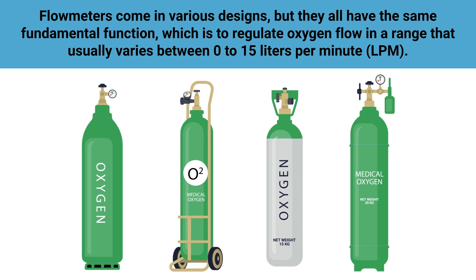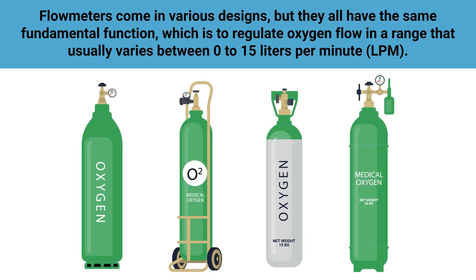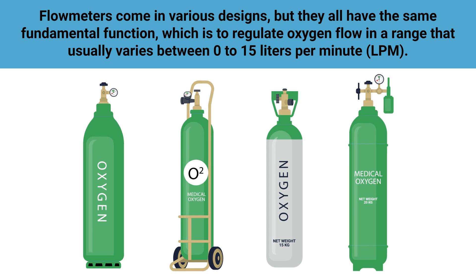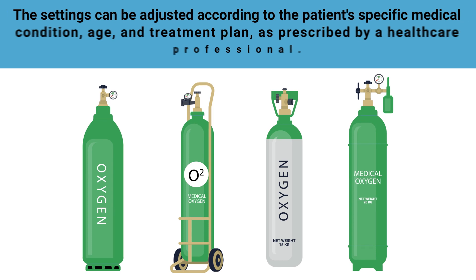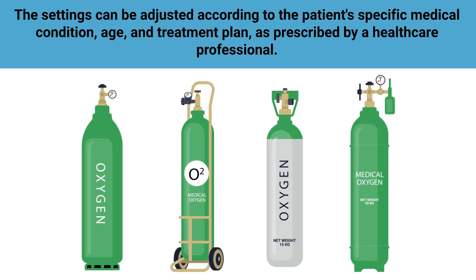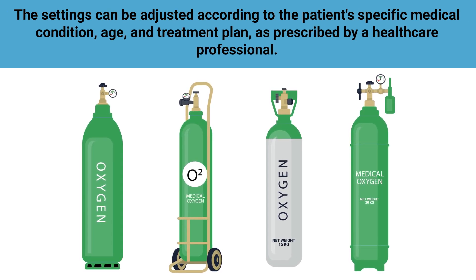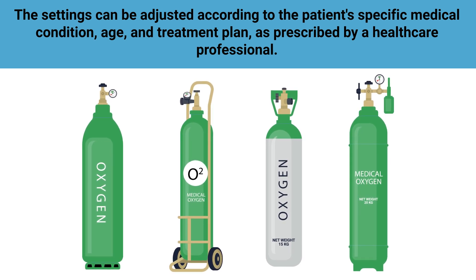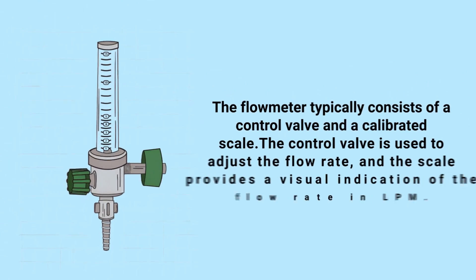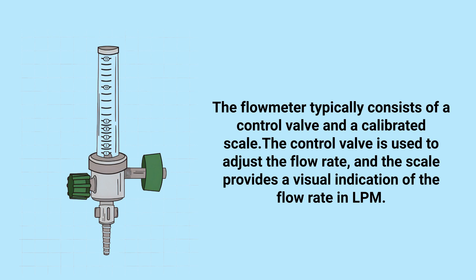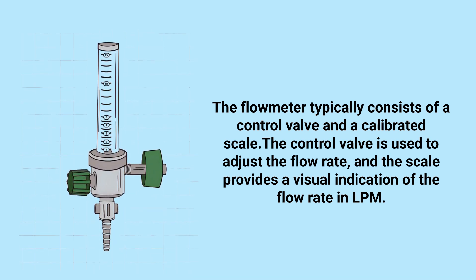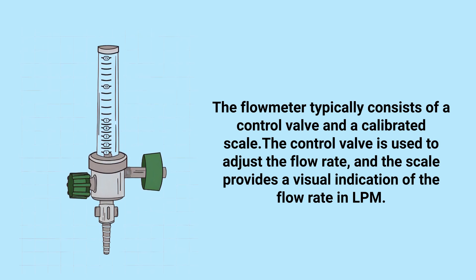Flow meters come in various designs but all share the same fundamental function: to regulate flow in a range that usually varies between 0 and 15 liters per minute. The settings can be adjusted according to the patient's specific medical condition, age, and treatment plan as prescribed by a healthcare professional. The flow meter typically consists of a control valve and a calibrated scale — the control valve adjusts the flow rate, and the scale provides a visual indication of the flow rate in liters per minute.